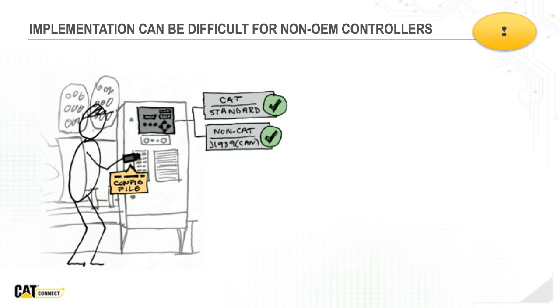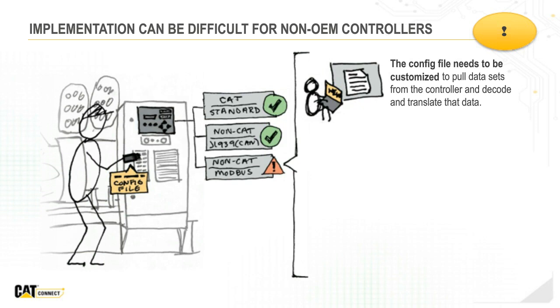Here we've got some examples between CAN, which is J1939, which follows a fairly standard approach if the controller software developer has followed the standard - that can be pretty standard across different controllers. When we get into Modbus, which is one of the most common protocols we see, there aren't any standards. So what we usually end up having to do is ask the provider of your controllers to get a list of their Modbus registers. That is non-standard. When we get those, that's where we create the custom configuration file that pulls the data sets and decodes and translates that data.